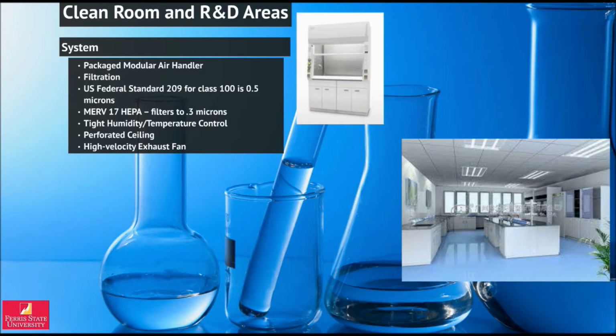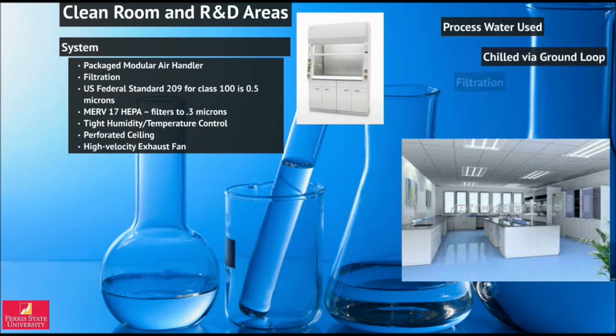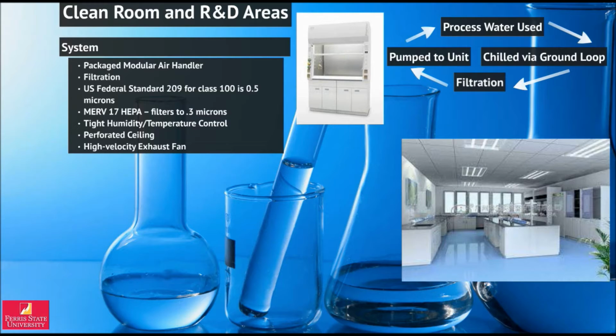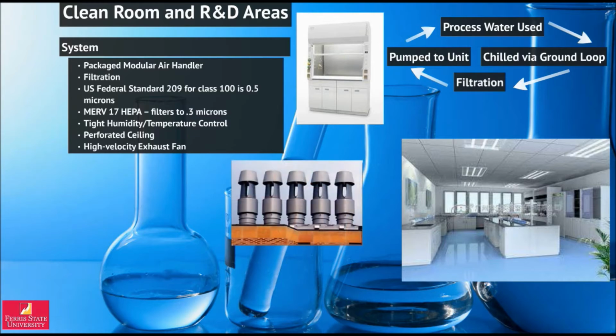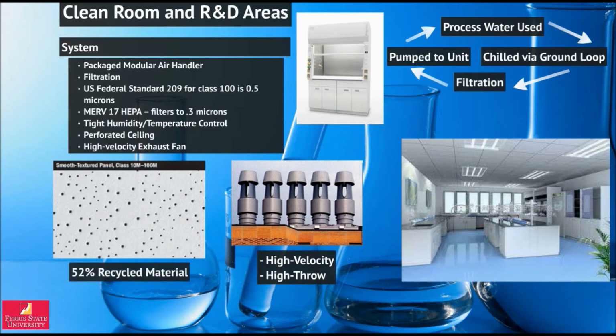The R&D areas also require their own process cooling water system. This process water is chilled through a ground loop configuration and then filtered to be used again in any water-cooled equipment within the laboratories. There are also multiple lab hoods within each R&D area that incorporate variable frequency drives and rapid response dampers on each exhaust fan. The exhaust fans selected for these hoods were high-velocity, high-throw exhaust fans that ensure contaminants being exhausted can be diluted to a less harmful level. Perforated ceiling tile comprised of 52% recycled material is utilized in the clean room and R&D areas to even out air distribution and control sound levels.